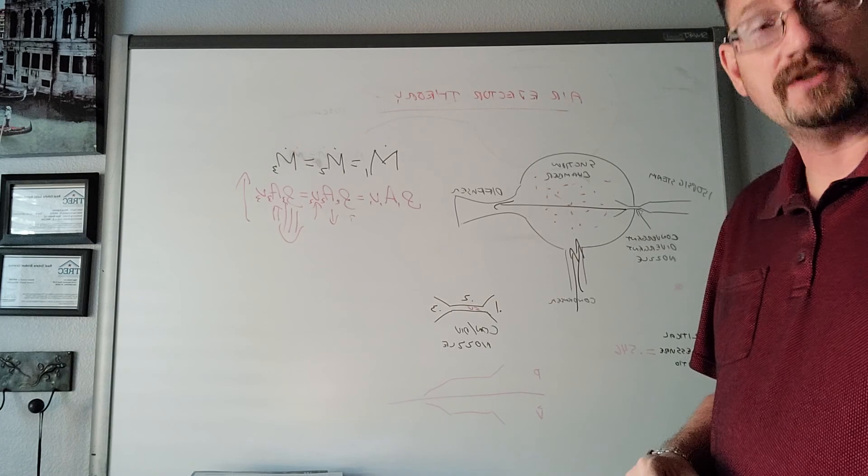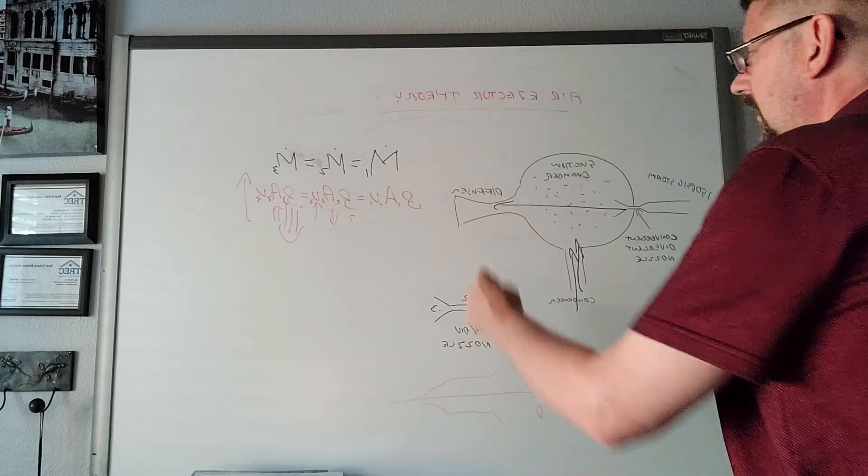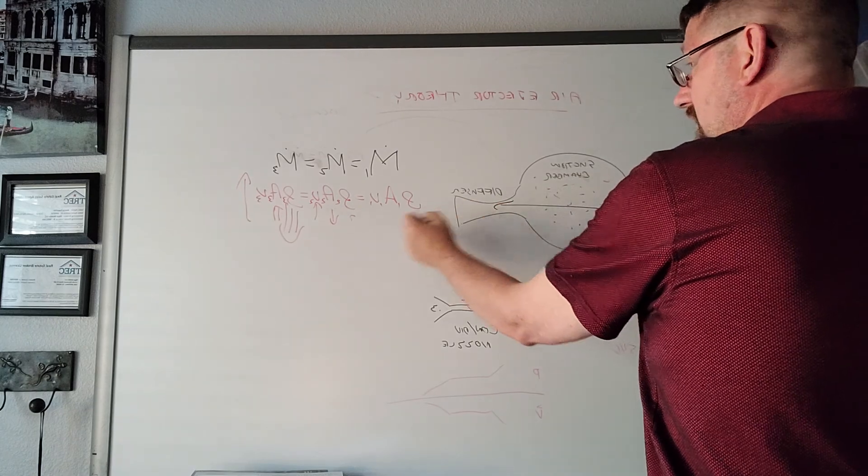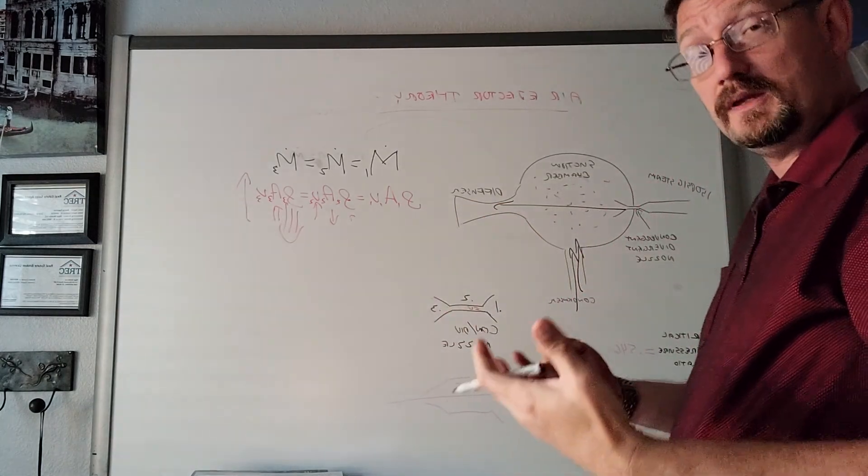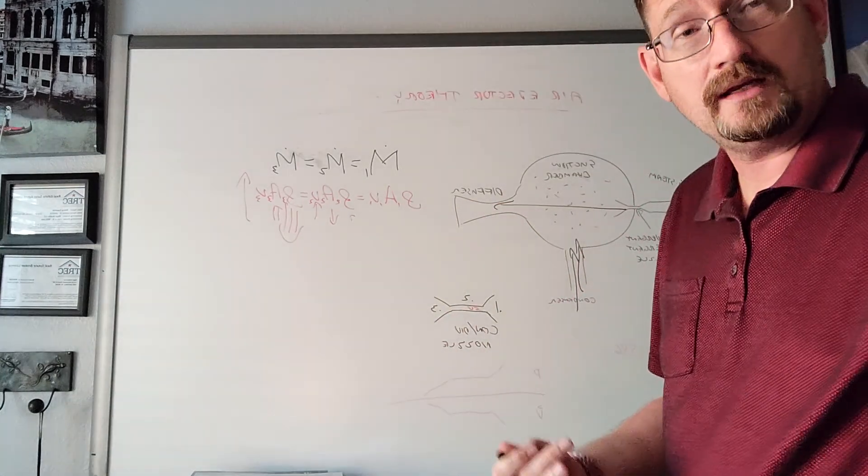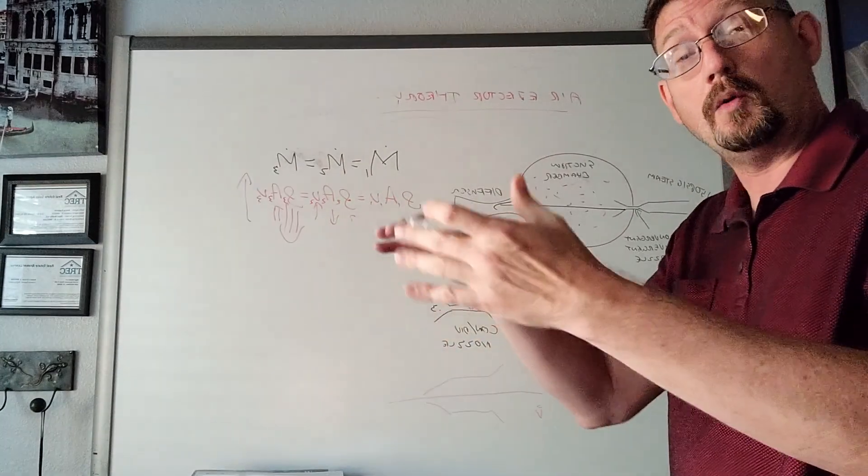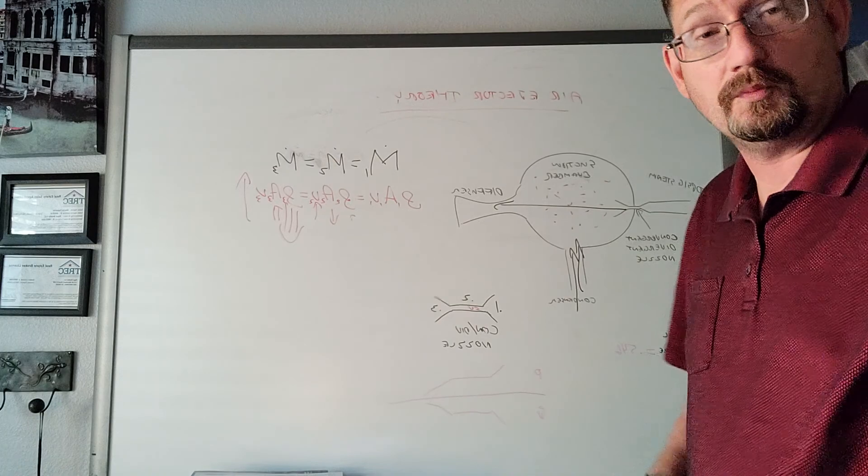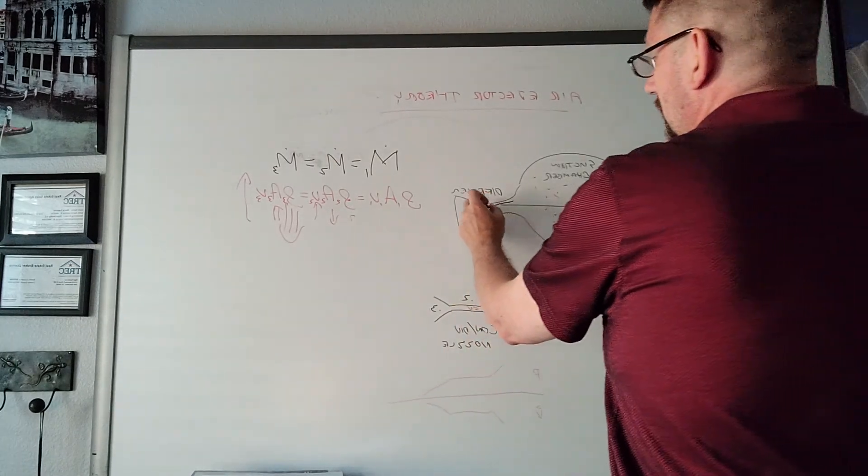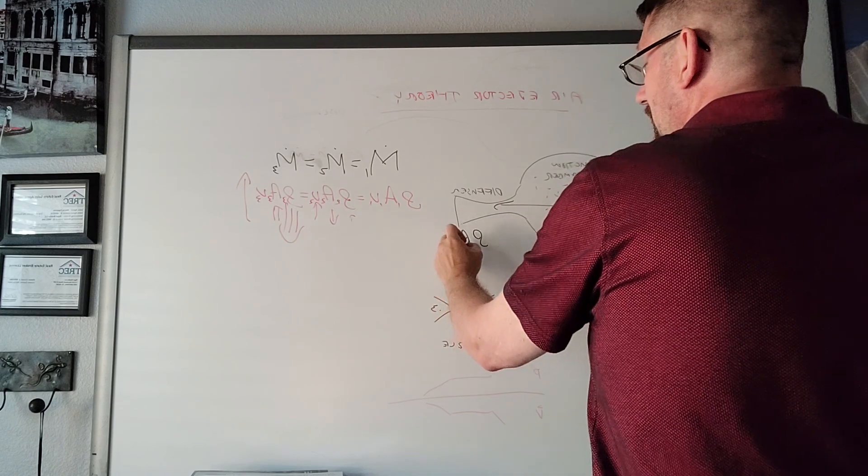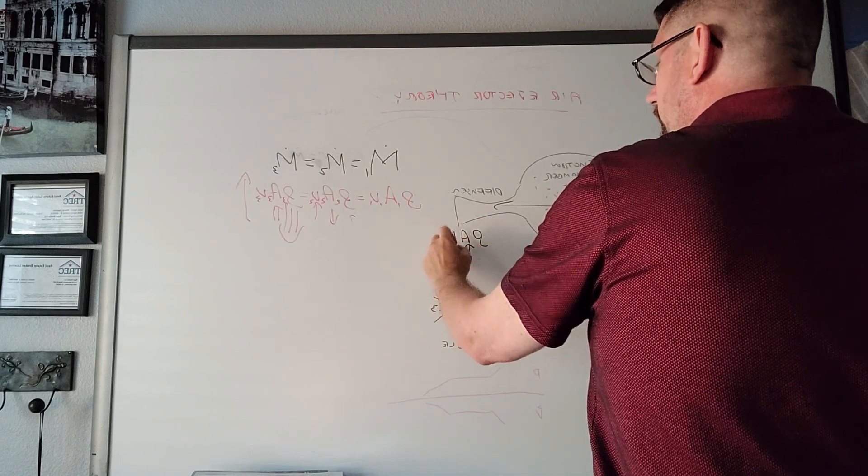In the diffuser, once it's molecularly entrained the air and non-condensable gas, it slows down a little bit. Those properties go back to where they were before they were supersonic. Area goes up, speed comes back down.